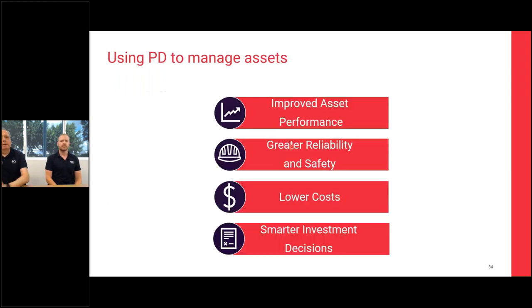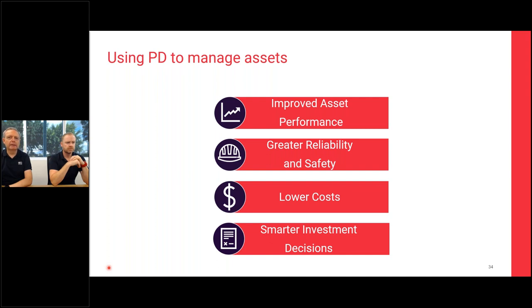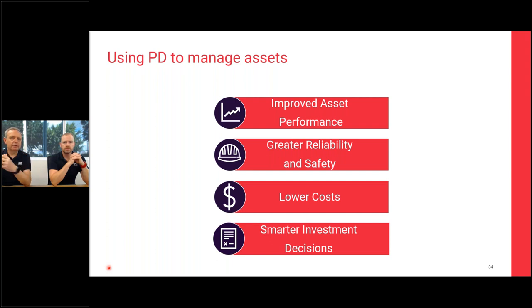If you get it right, it's the same as all techniques: you increase reliability, increase safety, improve network performance, and lower costs. The payback is relatively quick with a good number of assets. PD testing also informs condition-based asset management — if a younger asset is discharging while an older one is in good condition, why replace on age alone? This feeds into managing your asset population through condition and risk, a CBRM-type approach. PD is a really important tool for all high voltage assets.